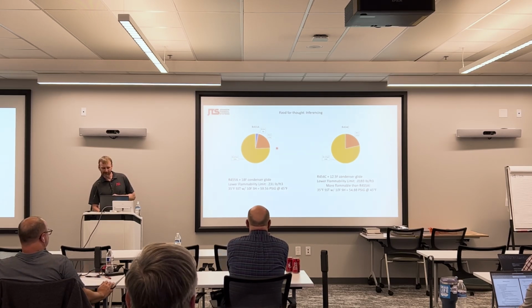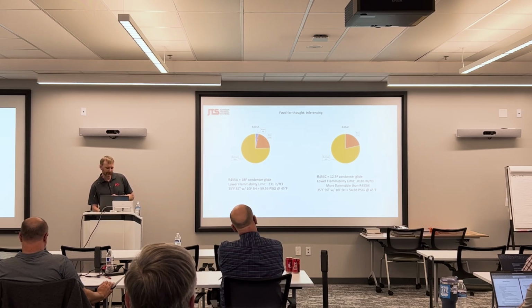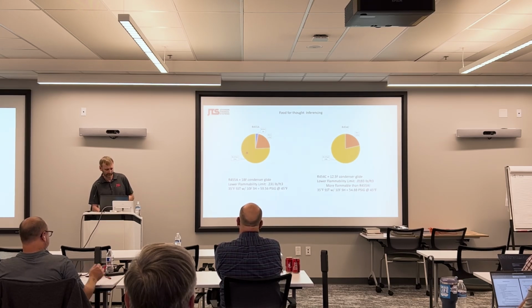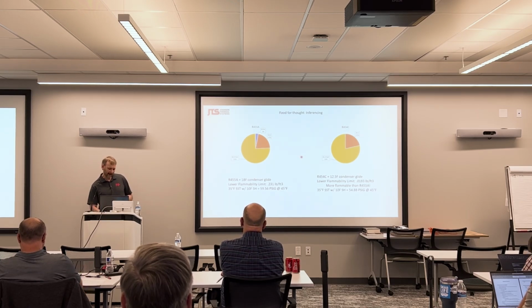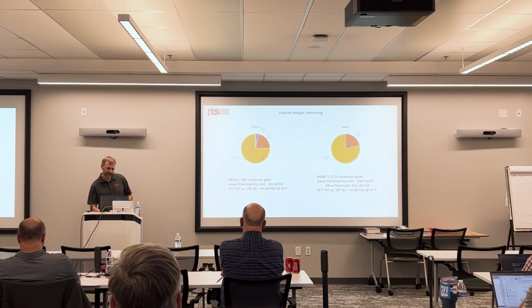There's a pretty good chance that it's going to start acting more like 454C. You're going to lose your CO2 component, and you're going to gain higher percentages of your R1234YF component. So if it starts acting more like 454C, there are some changes that happen. Due to this 3% CO2 component, R454A has significantly more glide. It's got 18 degrees of condenser glide versus R454C, which has 12.5 degrees of condenser glide.